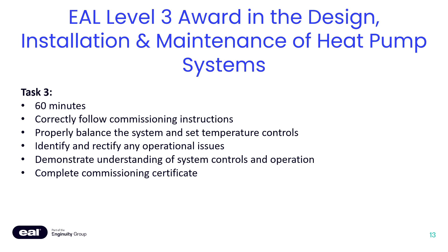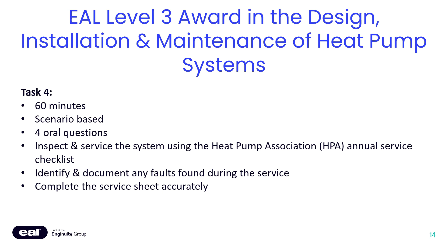And task 4, again 60 minutes, scenario based, is 4 oral questions relating to the inspection and service of the system using the Heat Pump Association annual service checklist. Identify and document any faults found during the service and complete the service sheet accurately. And that will then complete their assessment.